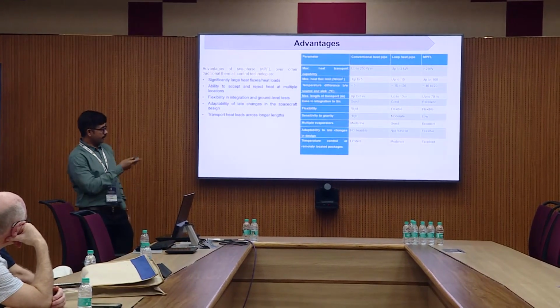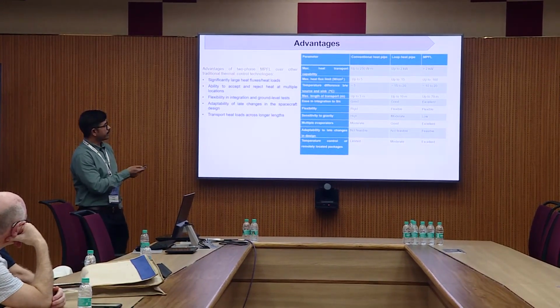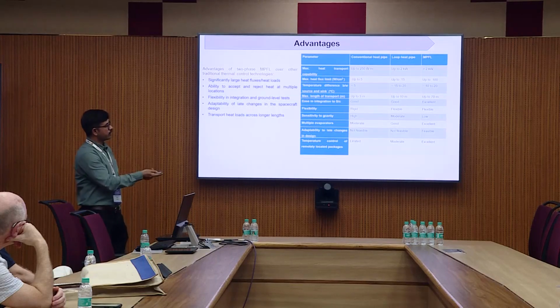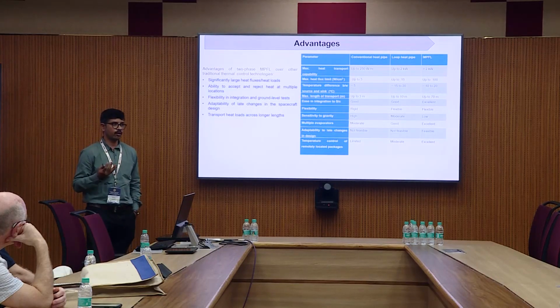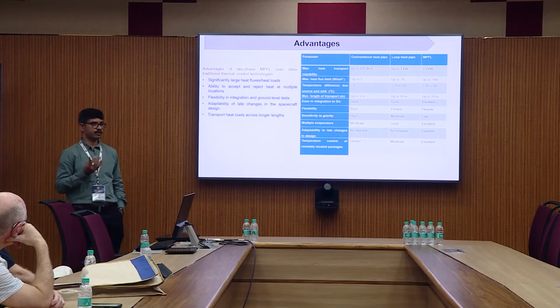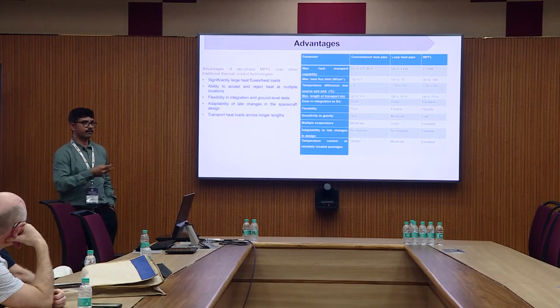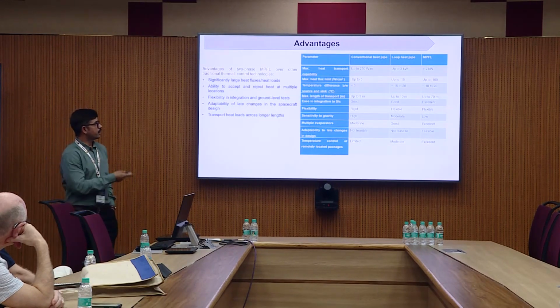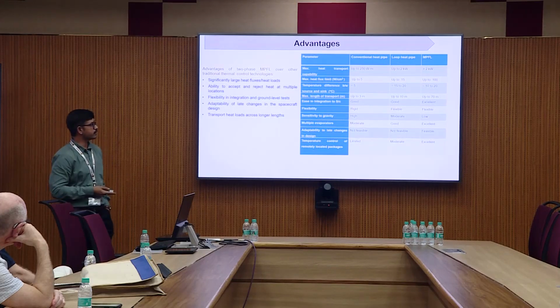You can see I have made a table of the maximum heat transport capability. Whenever there are more than 10 kilowatt spacecraft missions, we cannot use a loop heat pipe or this one; we have to use a pumped fluid loop. Heat flux is up to 100 watt per centimeter squared.